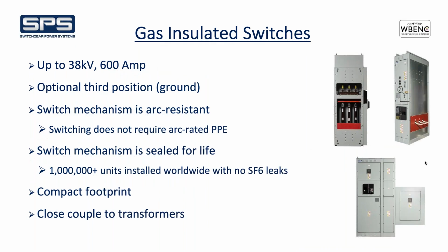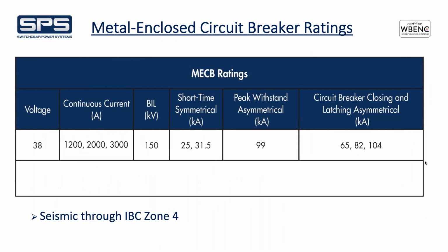So the flip side of the air insulated switch, we also offer a compact gas insulated switch. We utilize the Schneider switch mechanism for that. Same third position ground is available, sealed for life. That doesn't require arc rated PPE to do the switching. And like I mentioned, very compact footprint. Okay, so metal enclosed circuit breaker ratings. We're focused on 38 kV today, but we do apply the same principles to 5, 15 and 27 kV. But at this particular voltage, we offer up to 3000 amp, 1200 amp and 2000 amp also, and up to 31.5 kA.